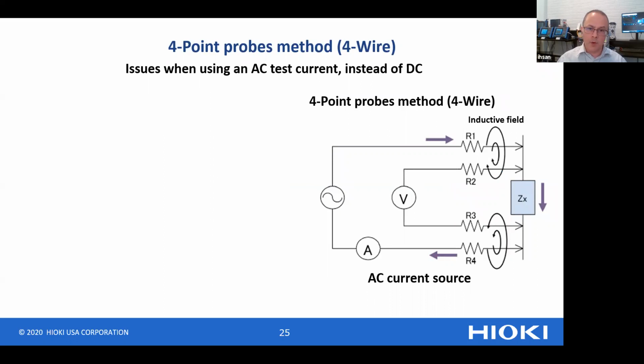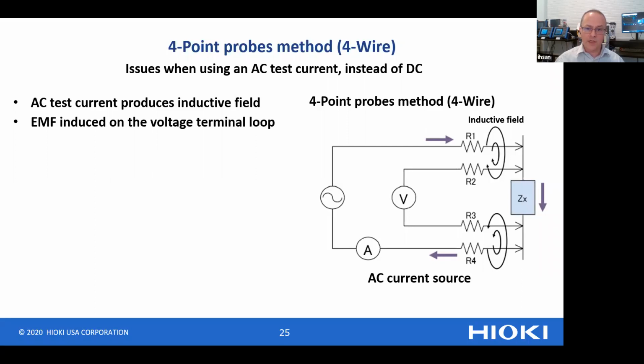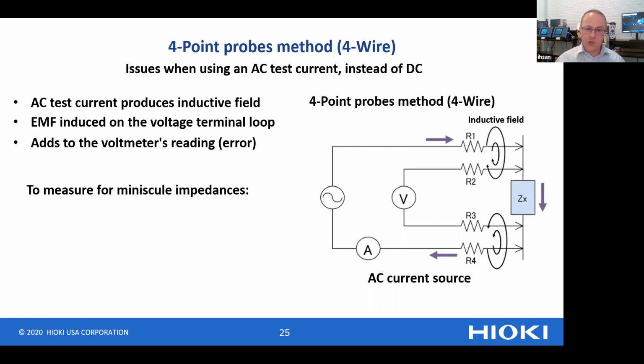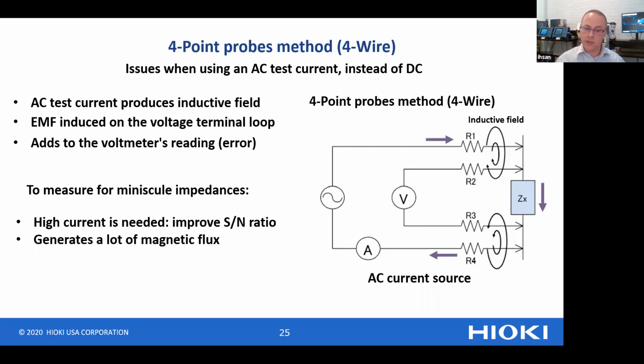Now, there are some issues with the 4-point probes method when you use AC test current instead of DC. As we know, with an AC test current, we have a change in the electromagnetic field. There's an inductive field that's rapidly changing, and this can induce an EMF or a voltage on the voltmeter loop. And this EMF that's induced in the voltmeter loop adds to the voltmeter's readings and is an error. For measuring minuscule impedances, we typically need a lot of current to get a good signal to noise ratio. And as high current generates a lot of magnetic flux, this increases the error at the voltmeter.